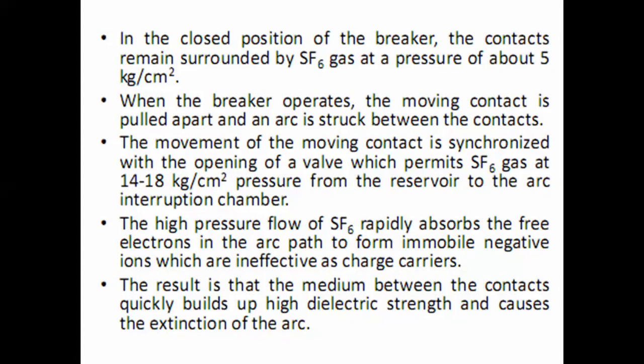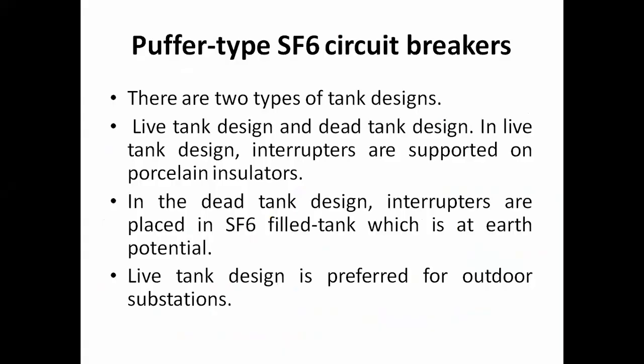The high pressure flow of SF6 rapidly absorbs the free electrons in the arc path to form immobile negative ions, which are ineffective as charge carriers. The result is that the medium between the contacts quickly builds up its dielectric strength and causes the extinguishing of the arc. And in this way, your circuit breaker can operate.